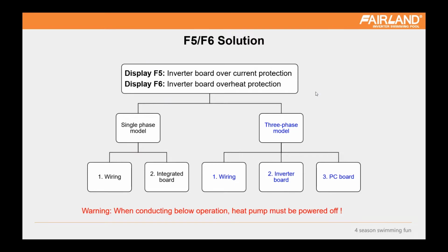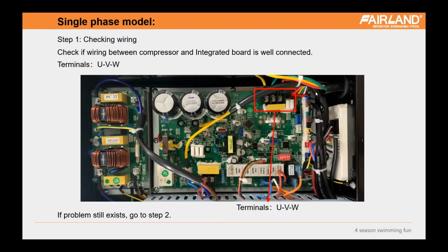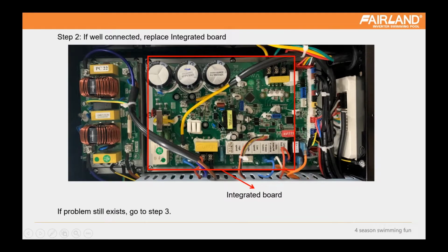F5, F6 is the overcurrent protection, overheat protection. It's a protection function about the compressor, this integrated board, including the driving module for the compressor. So we will check the same terminals U, V, W to see if they are well connected, and if not, we will replace the integrated board.